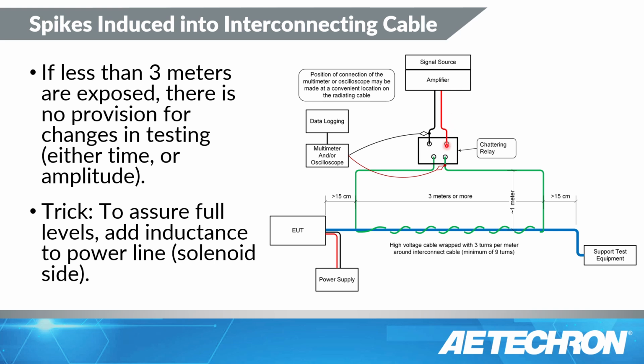This is powering the relay coil. The relay coil is essentially in this leg, and from the output of the relay coil, it wraps around and comes to a normally closed relay switch here, so that as you energize that relay coil, it opens up the switch. So it breaks its own contact. Well, you've got a lot of current flowing through here, and all of a sudden you're opening that switch. This has to be an unsuppressed relay. In other words, there's no filter across that relay contact. As that opens, it arcs, and there's the source of your noise.